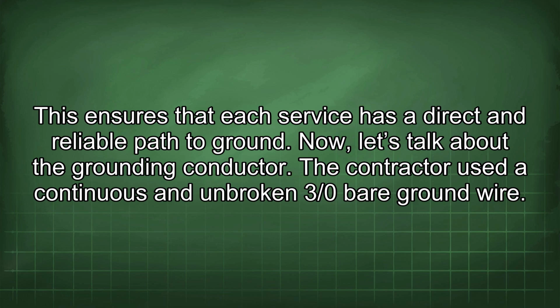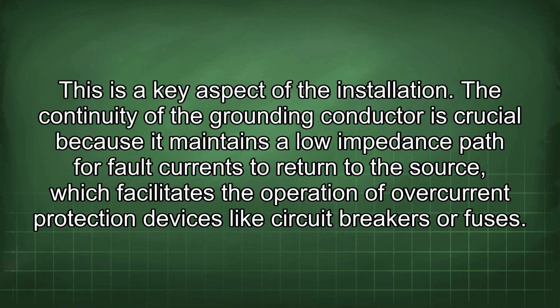Now let's talk about the grounding conductor. The contractor used a continuous and unbroken 3/0 bare ground wire. This is a key aspect of the installation. The continuity of the grounding conductor is crucial because it maintains a low impedance path for fault currents to return to the source, which facilitates the operation of overcurrent protection devices like circuit breakers or fuses.